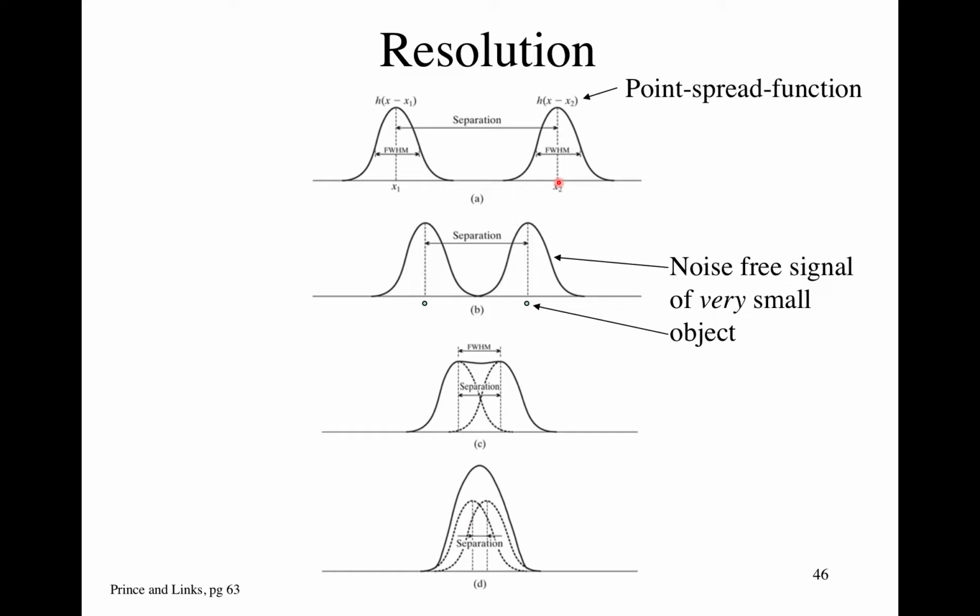Sometimes we take a cheap ballpoint pen and remove the ballpoint, which gives you a really hard little metallic sphere. You image that, and it's well below the basic pixel size of the picture you're going to make. And then when you image that thing, what you get is a Gaussian function. It's a blurred picture of that dot that is quite tiny. You can't resolve that thing in your imaging system.